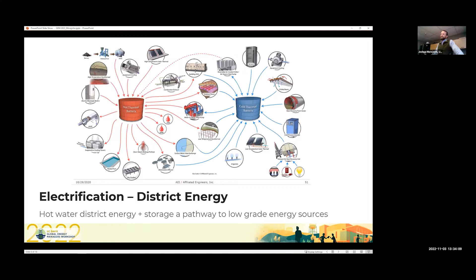A lot of that is enabled with a water-to-water heat pump or heat recovery chiller. So we looked at a lot of those opportunities — the big one for us was our cooling system, since we already had all this heat we could use. We looked at our existing steam system, and this is a life cycle cost analysis.